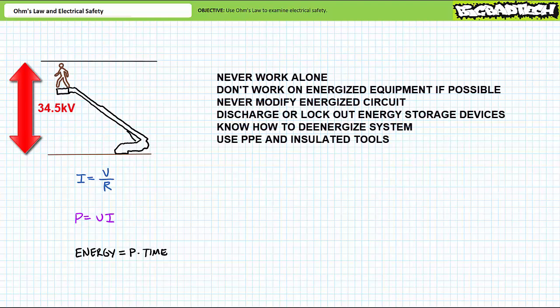Here's some general safe work practices you should follow in working with electricity. Never work alone. If your team is working remotely stay in contact with the operations and maintenance organization using radios. Turn the power off. Certain measurements must be made with the power on but if all possible turn it off when connecting instrumentation and turn it back on to make the measurement. Never modify a circuit with the power running. You could accidentally short circuit critical current controlling elements. This is especially important when incorporating ammeters into a system. High power circuits need to make and break connection using devices rated to make and break that high current. Discharge or lock out any electrical energy storage elements like batteries or capacitors. Even if this system is unplugged such energy storage devices can energize this system.